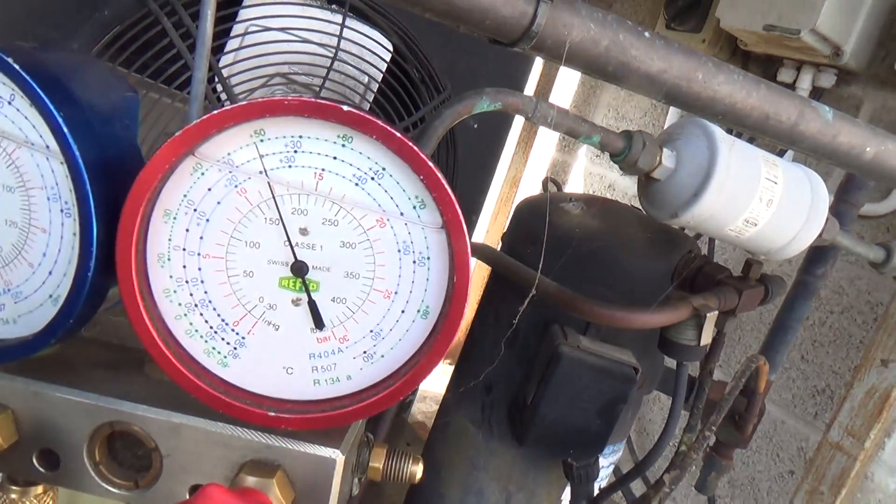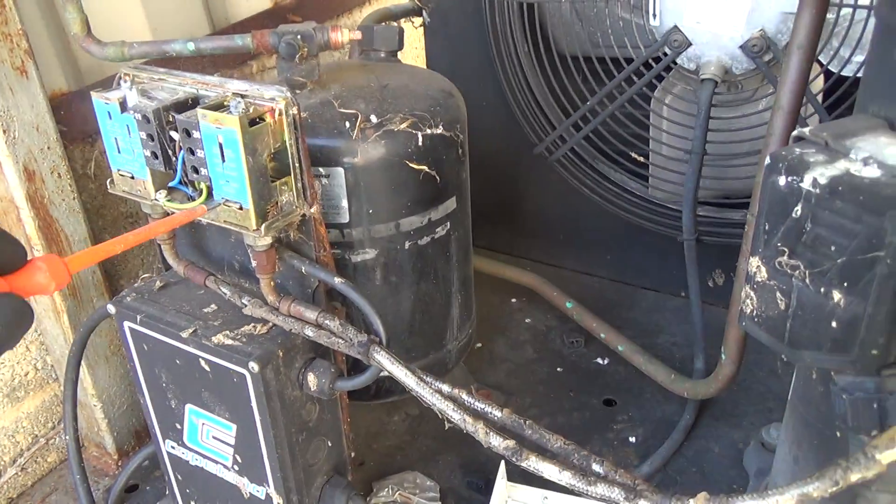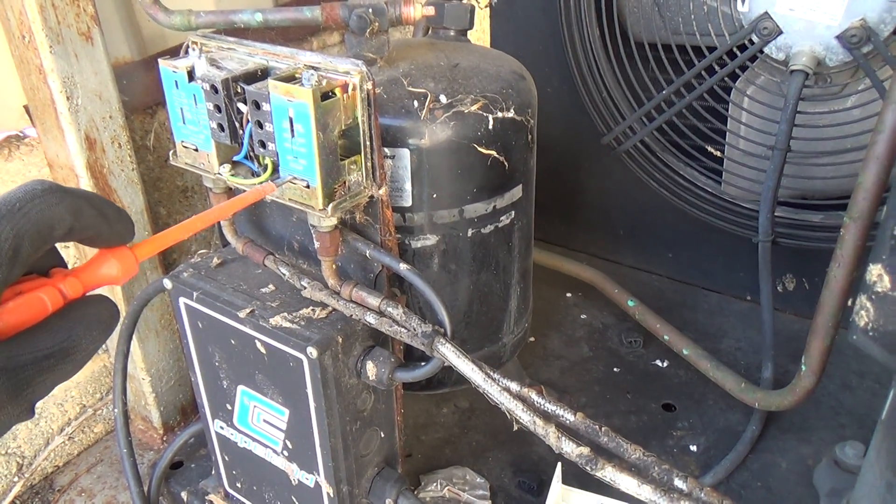Your standing pressure's only 170, and that's a set point of 400, so 20 psi differential maybe. Should cut back in at 380.